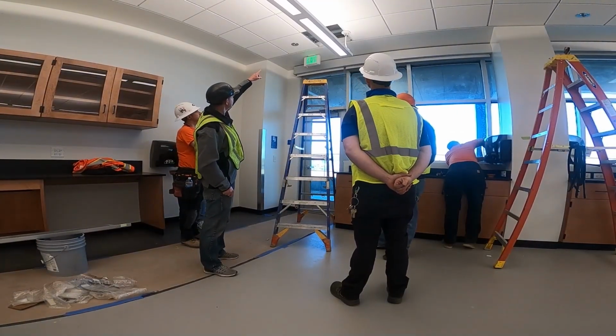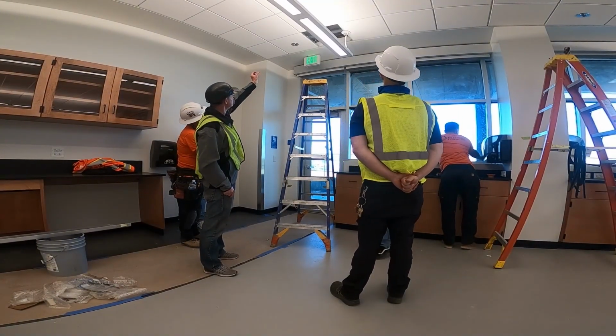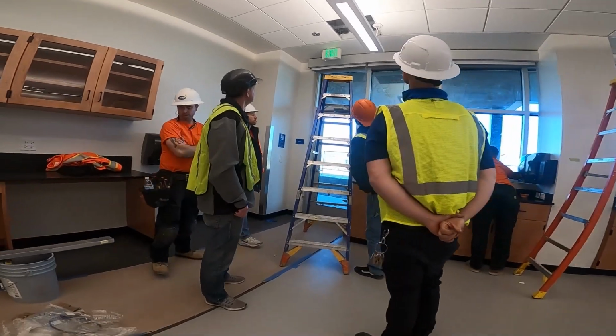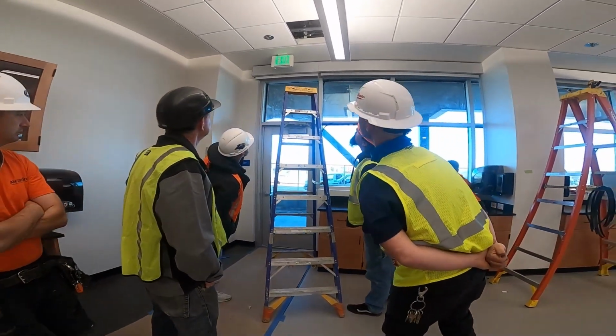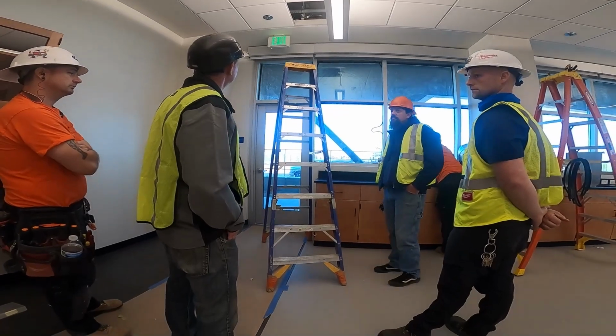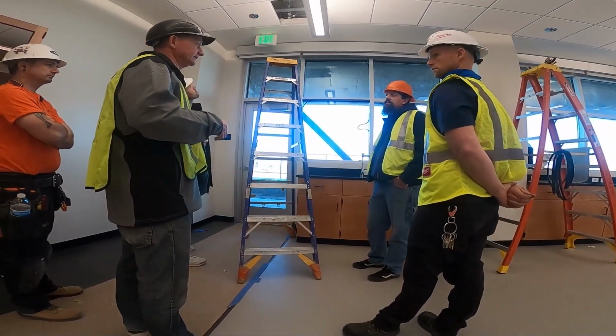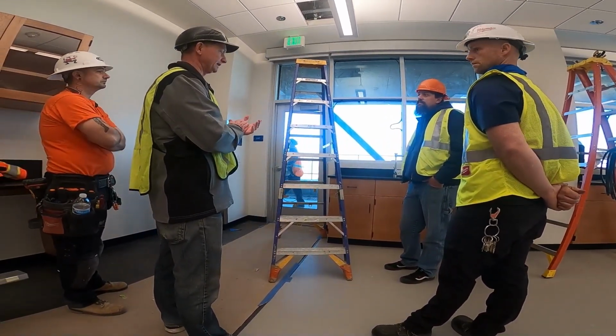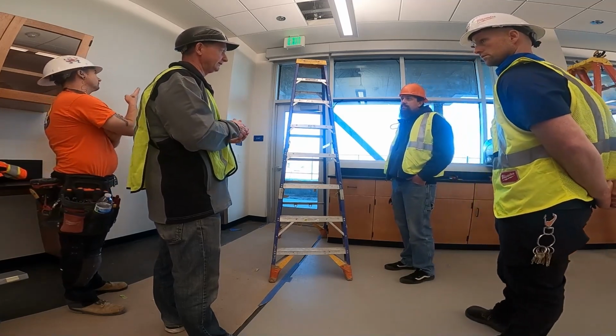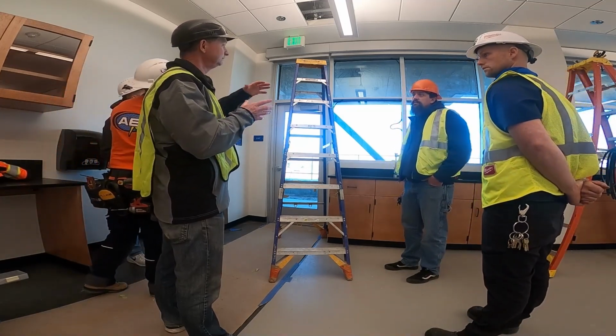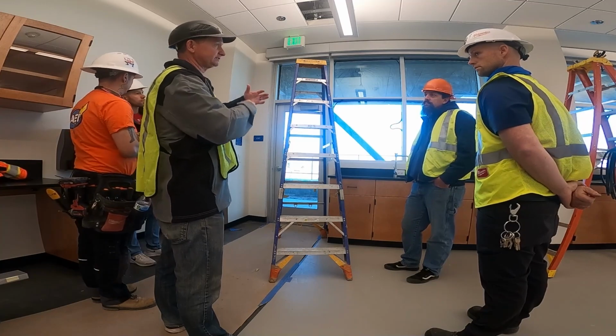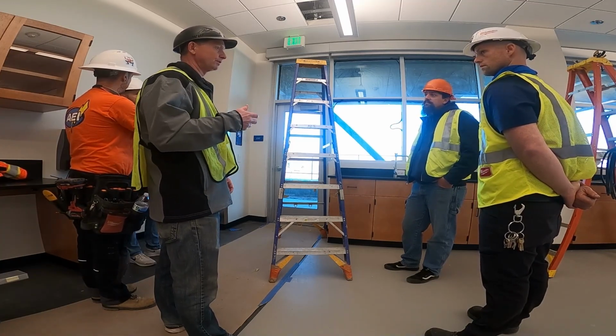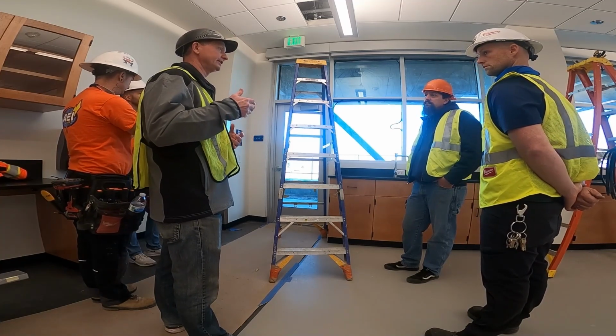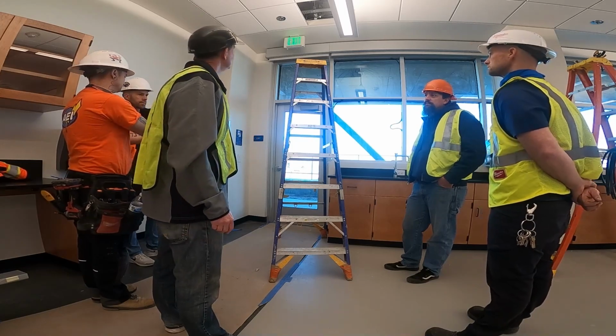Then you can see the tiny little blue section right to the right of that terminal block for dimming. That's going to be your occupancy vacancy settings. And it comes, there's 4 of them, and it comes all of them off. And if you want it to be occupancy, you can look at what the existing one is and just match those dip switches. 3 and 4 will, if you turn those on, that will be an occupancy setting.